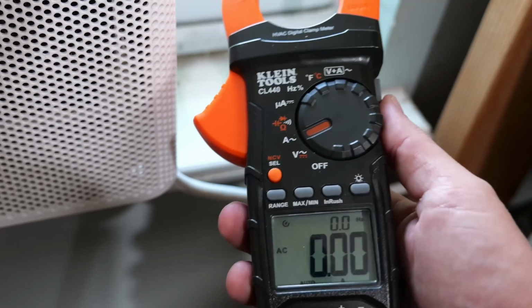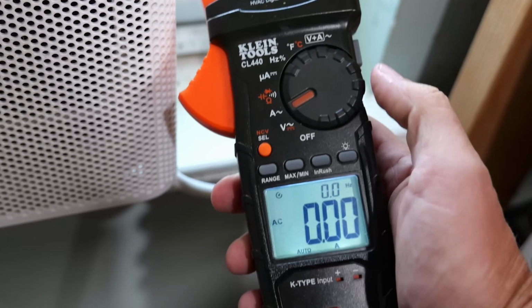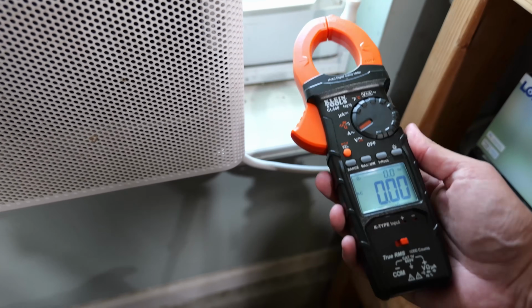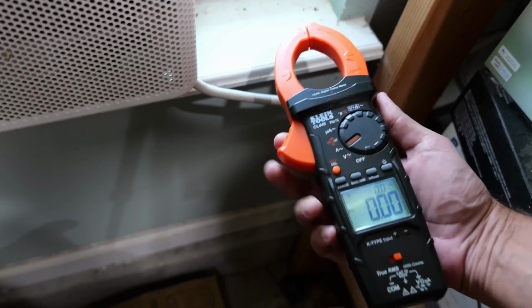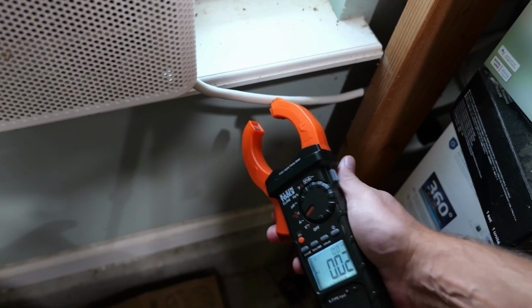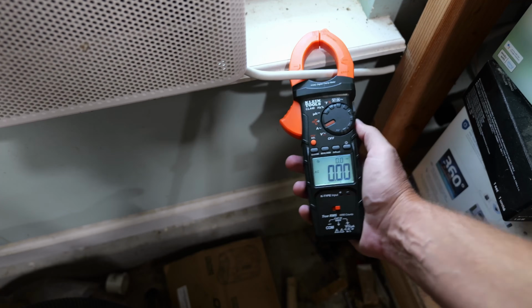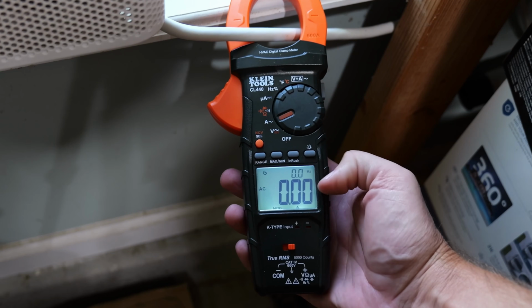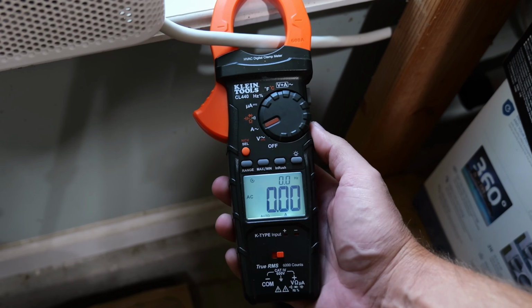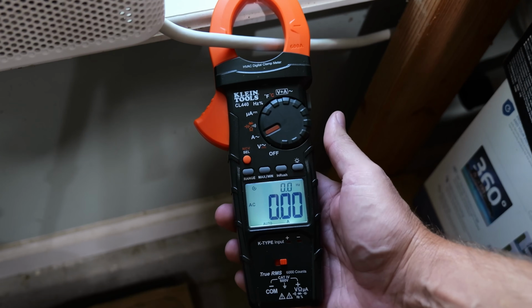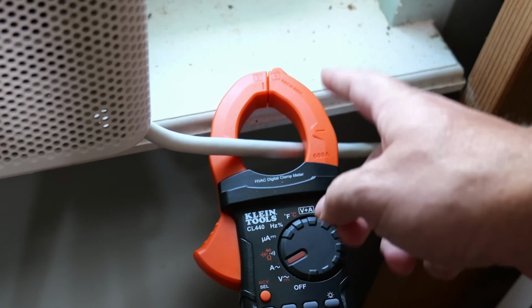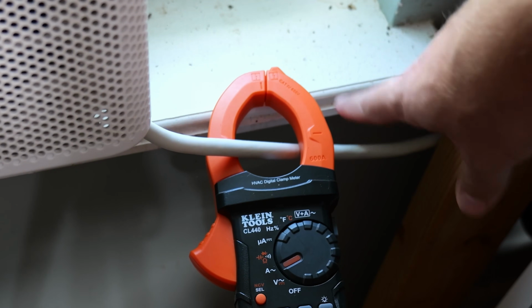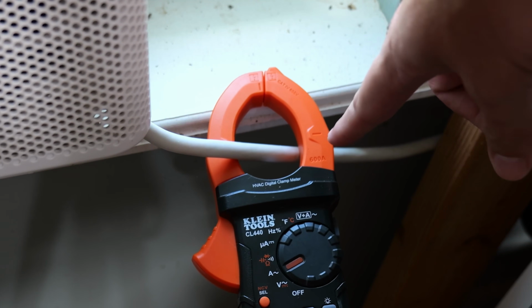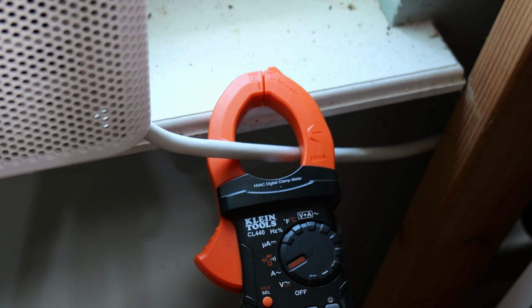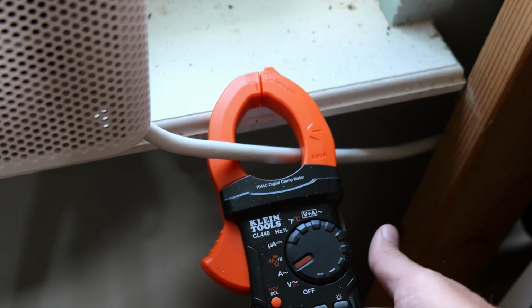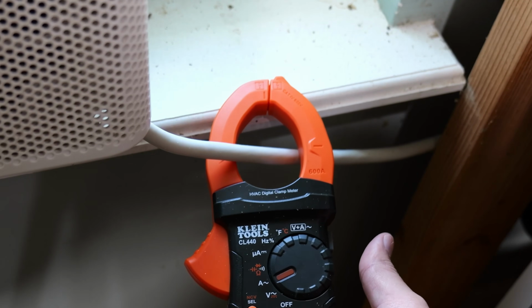Now we're ready to read the amperage of whatever it is we're wanting to test. All I need to do is take my clamp, open it up, put it around my wiring, and get my amperage reading. But as you can see, we're not getting a reading whatsoever, it's reading 0. You might be wondering why. The problem is, since I'm putting it around the power cord to the AC unit, inside this cable is not just the hot wire supplying the current, but the neutral and ground are in there as well. When they're all combined together inside the clamp, you're not going to get a reading, they cancel each other out.